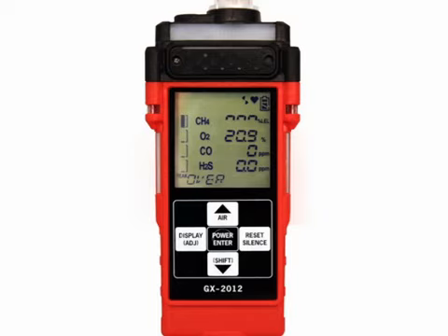Follow your established procedure for an increasing gas condition. Reset the alarm using the Reset Silence button once the alarm condition has cleared. Calibrate the GX-2012 as described in the calibration section of the manual. If the overrange condition continues, you may need to replace the sensor that has triggered the overrange alarm. If the overrange condition continues after you have replaced the sensor, contact RKI Instruments for further instructions.